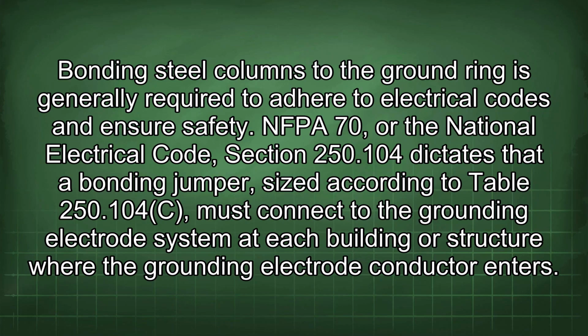Bonding steel columns to the ground ring is generally required to adhere to electrical codes and ensure safety. NFPA 70, or the National Electrical Code, Section 250.104 dictates that a bonding jumper, sized according to Table 250.104C, must connect to the grounding electrode system at each building or structure where the grounding electrode conductor enters.